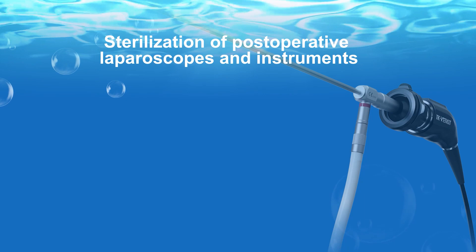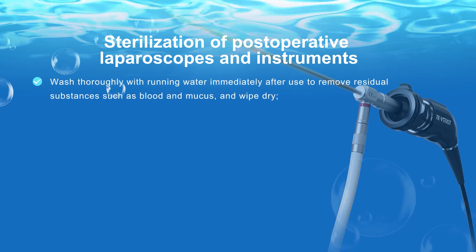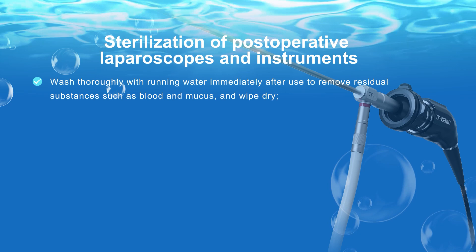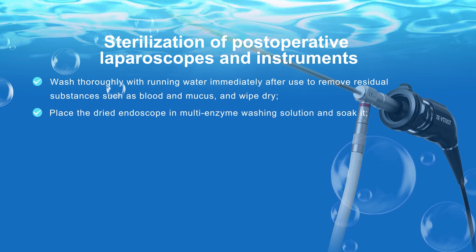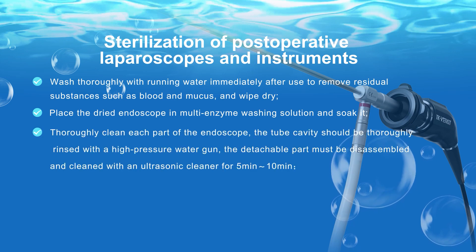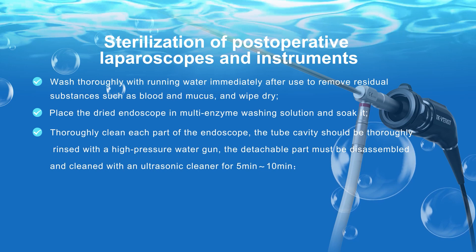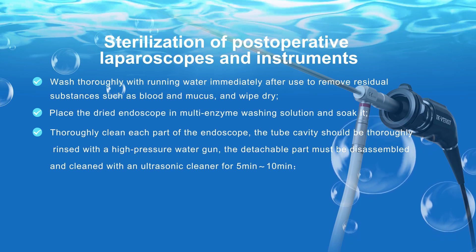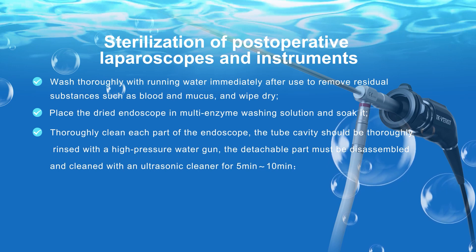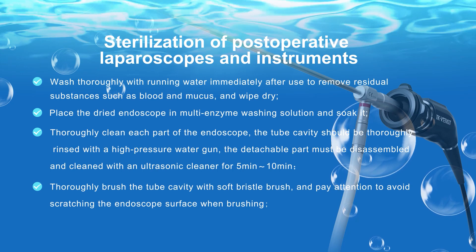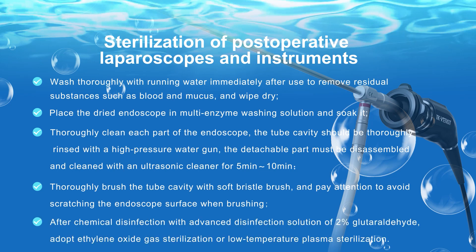Sterilization of post-operative laparoscopes and instruments. Wash thoroughly with running water immediately after use to remove residual substances such as blood and mucus, then wipe dry. Place the dried endoscope in multi-enzyme washing solution to soak, and thoroughly clean each part. The tube cavity should be thoroughly rinsed with a high-pressure water gun. Detachable parts must be disassembled and cleaned with an ultrasonic cleaner for 5–10 minutes. Thoroughly brush the tube cavity with a soft bristle brush, taking care to avoid scratching the endoscope surface. After chemical disinfection with 2% glutaraldehyde advanced disinfection solution, adopt ethylene oxide gas sterilization or low-temperature plasma sterilization.